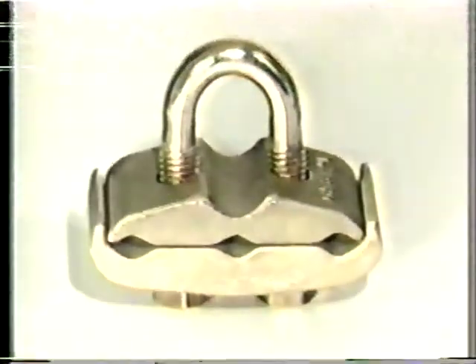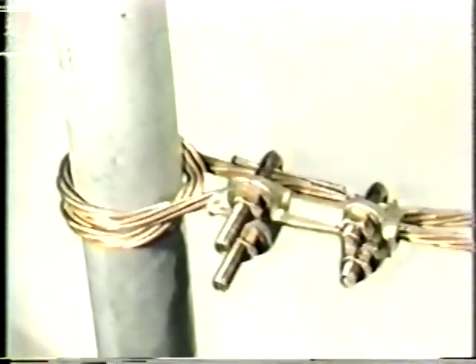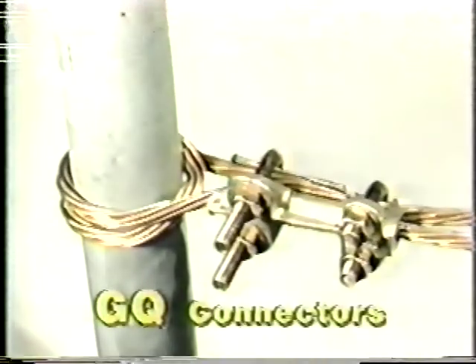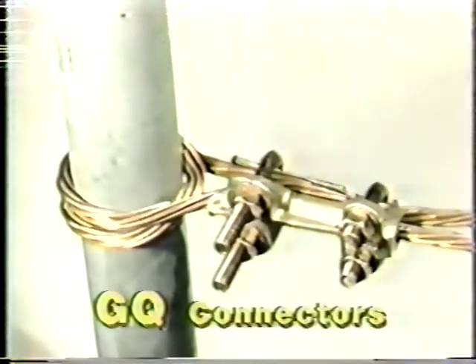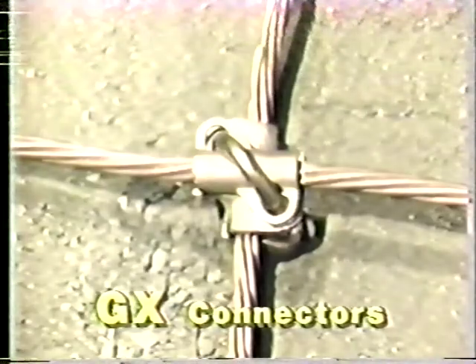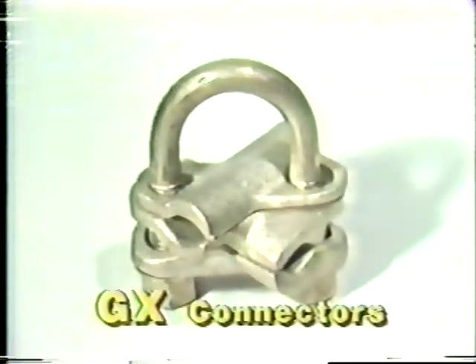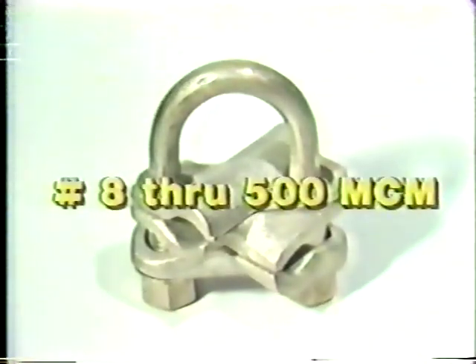For connecting cable to larger posts or pipes, the Burndy GQ series of connectors enable you to accommodate virtually any large diameter post. The Burndy GX connectors are designed for cross-grid cable applications, including UL-listed direct burial installations. They too are range-taking and can accommodate conductors from number 8 through 500 MCM.